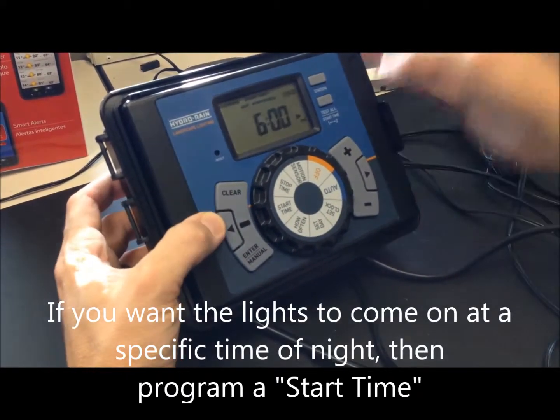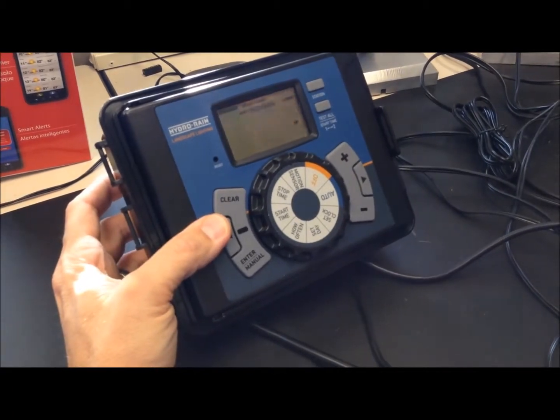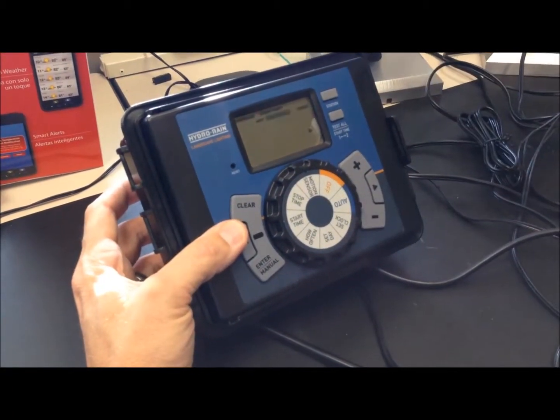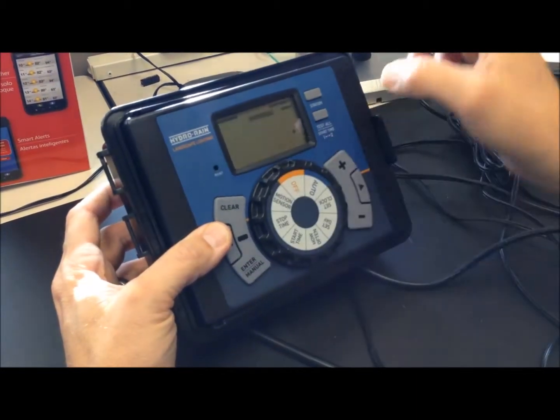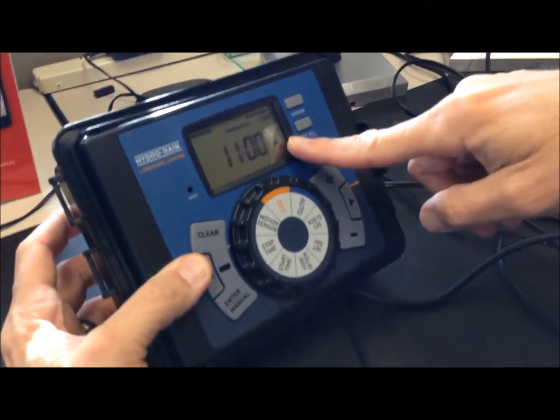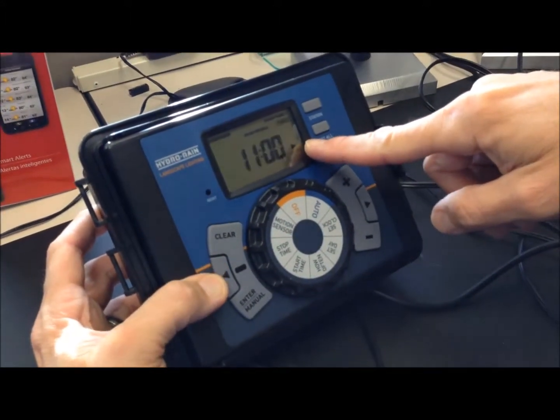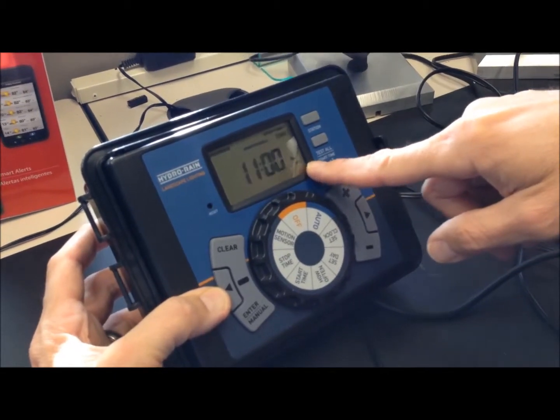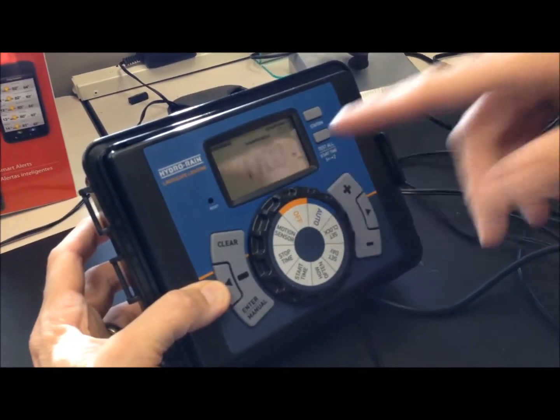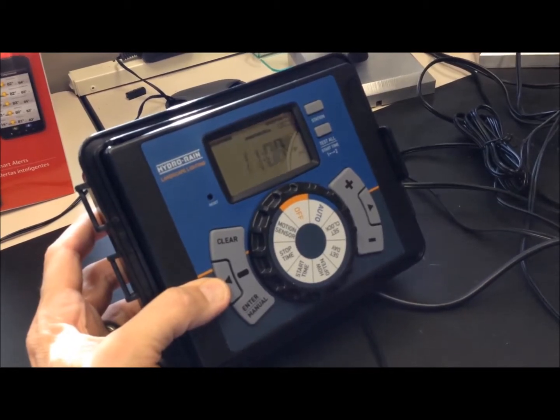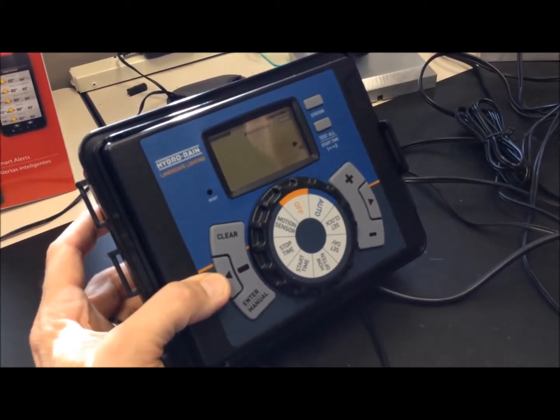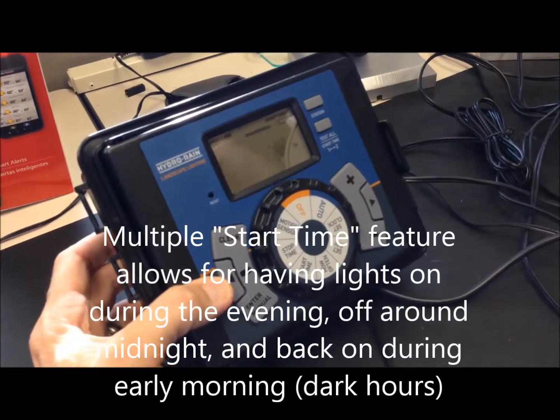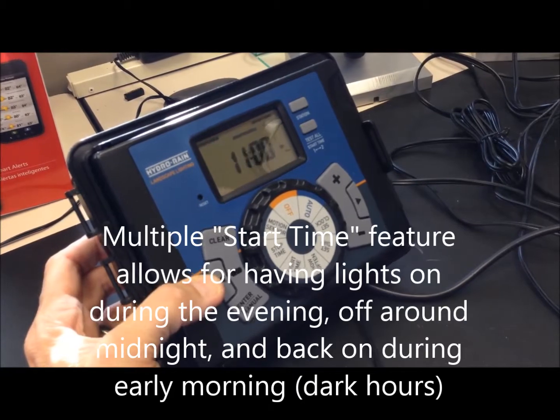So for an example, you could start in the evening. You can use the photocell to bring your lights on. And then you can go to a stop time and have an actual time set for the stop time. The advantage of this is that now you can use your second start time. Instead of having your lights run all night long, they come on in the evening when people can see them, then they go off late at night. And then you can have them come on again in the morning if you'd like so that you have light if you leave early in the morning.